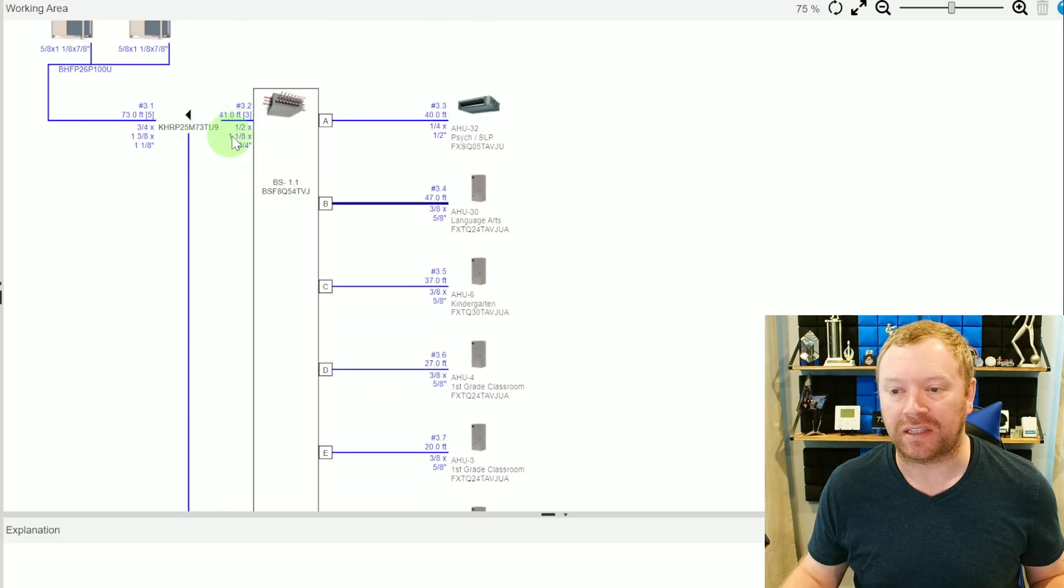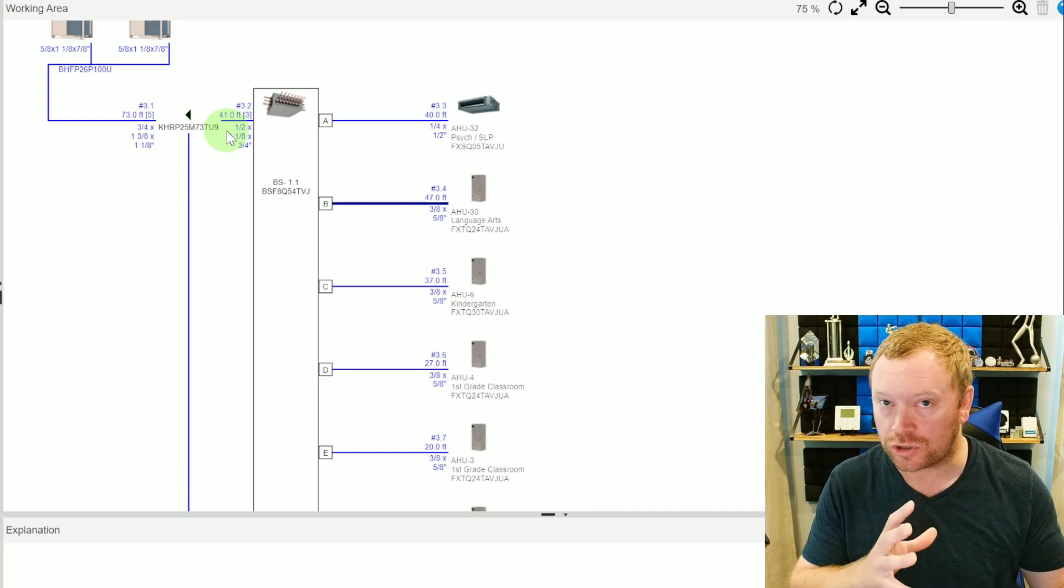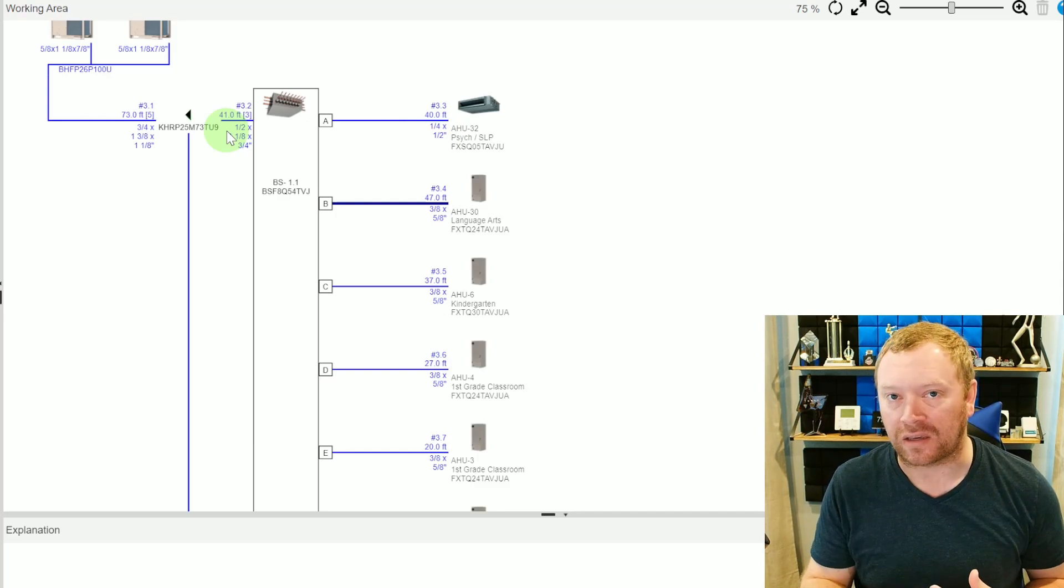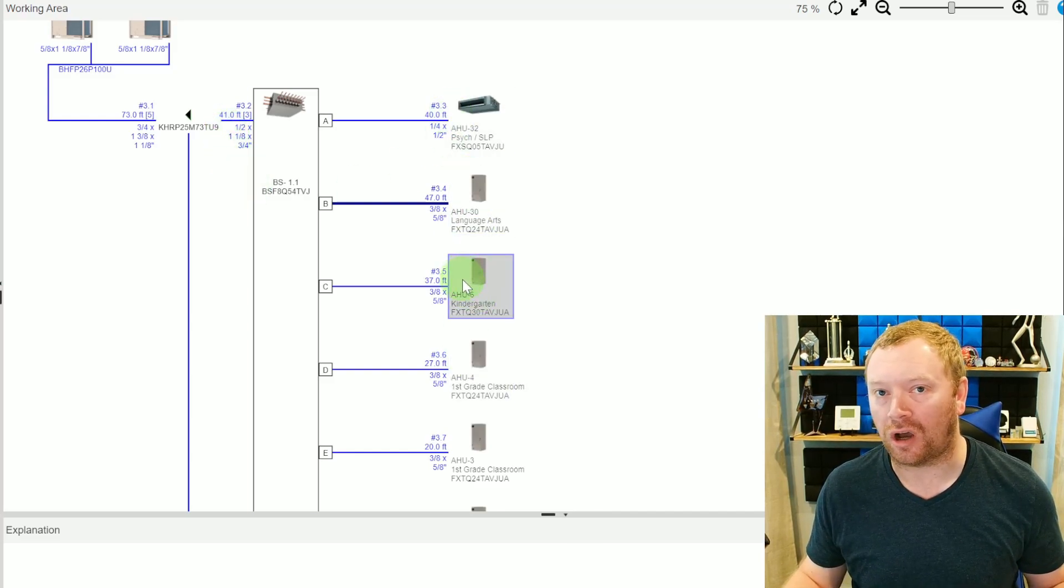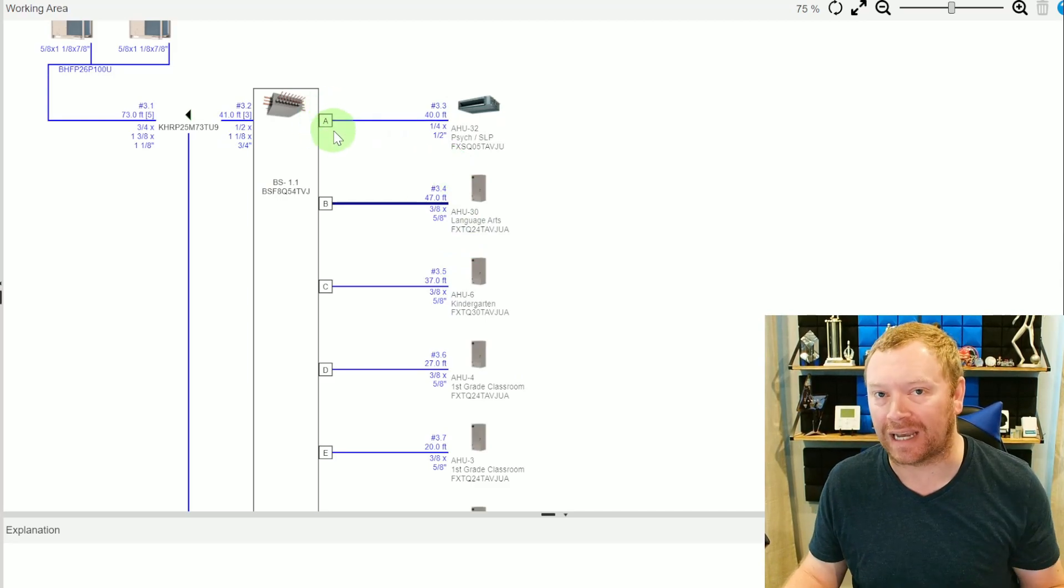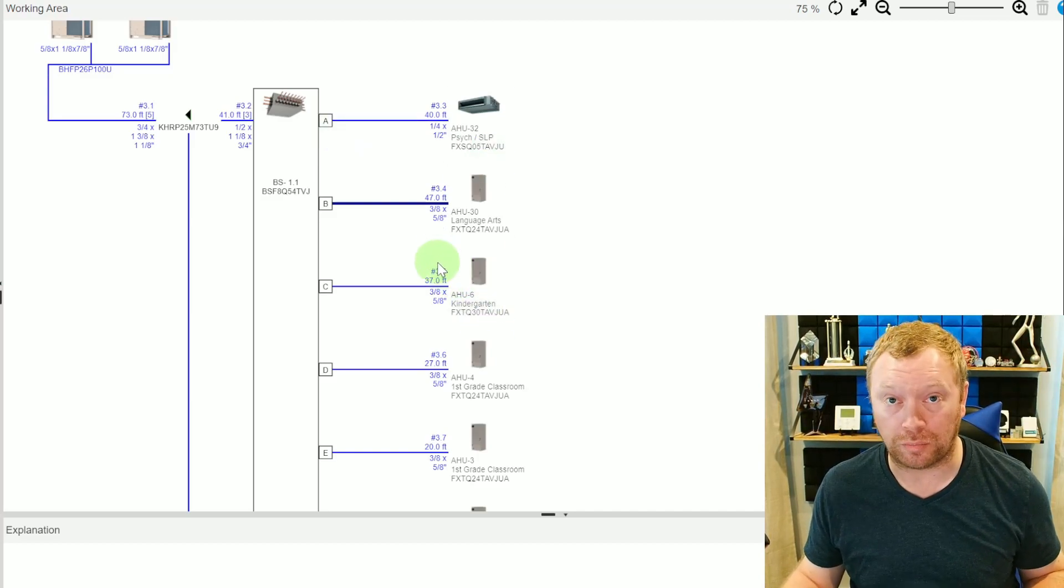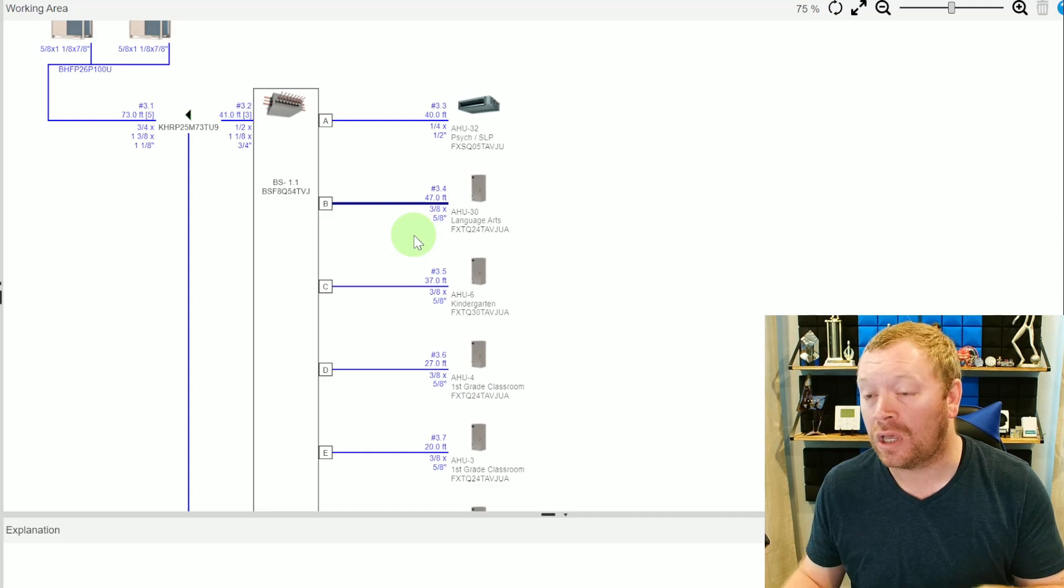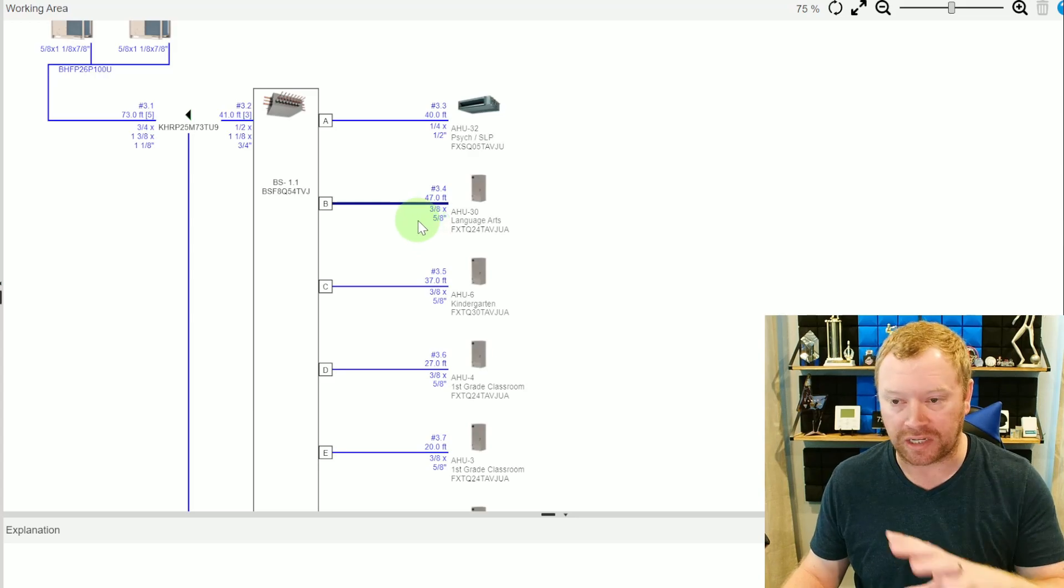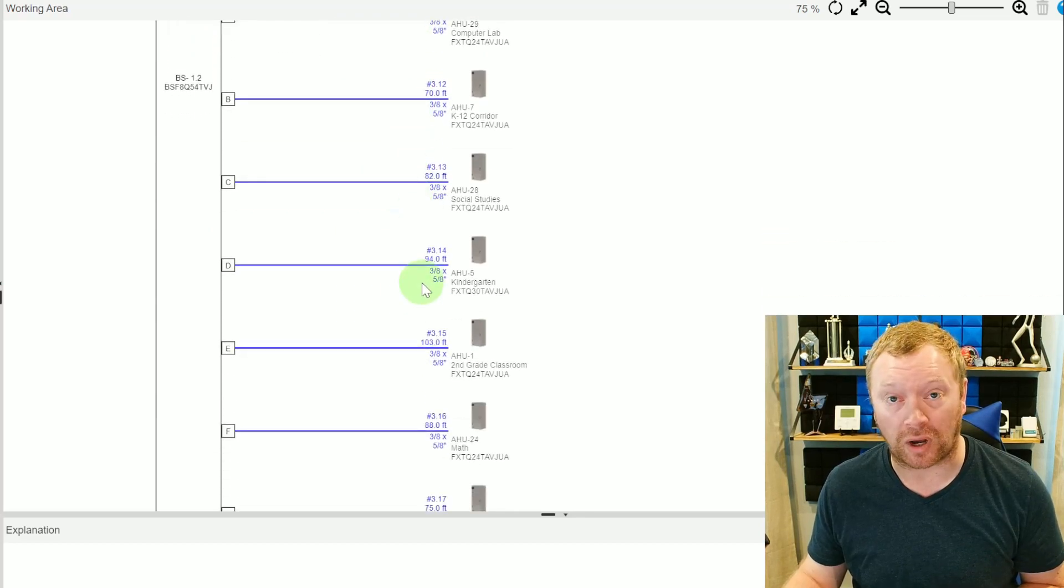But Dana, they're the same branch box. Yes, they are. But what's your downstream capacity? Remember that I said these pipe sizes are both sized or calculated to be sized based on downstream connected capacity to that pipe and the length. What happens very commonly is these indoor units do not get installed on the exact box of the exact port that we pre-design these units to get installed on. Sometimes these indoor units will move around from port to port, which is fine. You just need to make note of that so that when we build an as-built, we have a correct as-built. So that way we know if something's cross-wired, which port is supposed to be which.